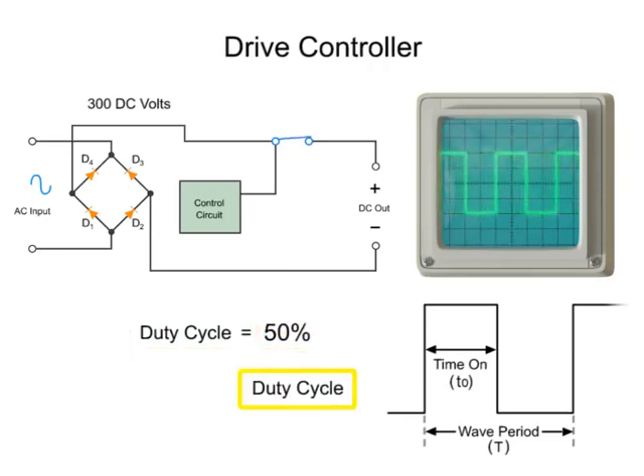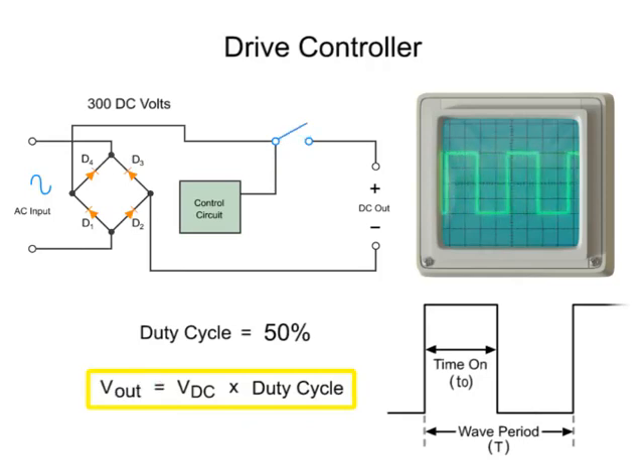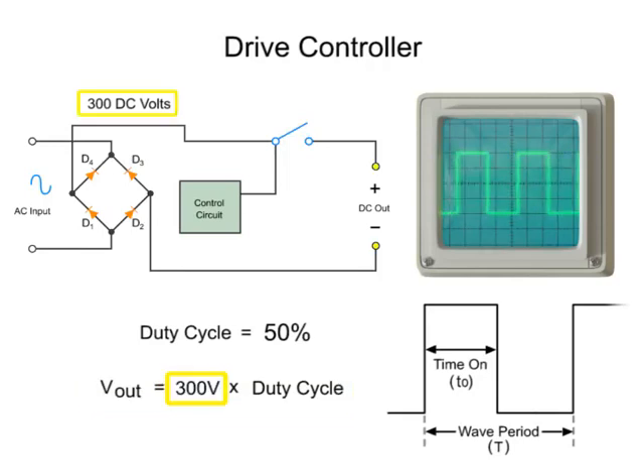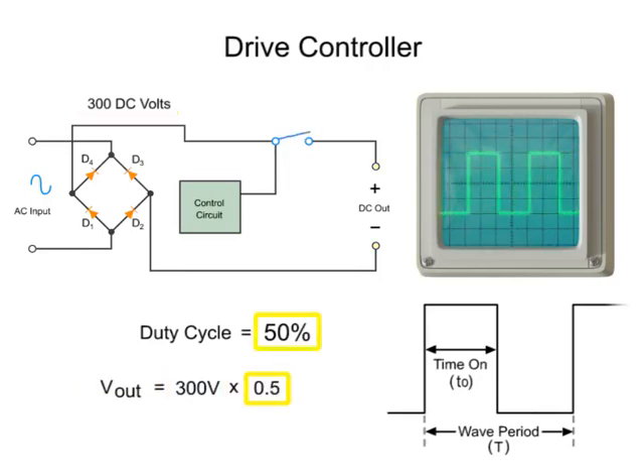Multiplying the duty cycle times the input voltage will give you the voltage output. In this example, a 300 volt input will be modulated by 50%, so the final voltage delivered to the load or motor is 150 volts.